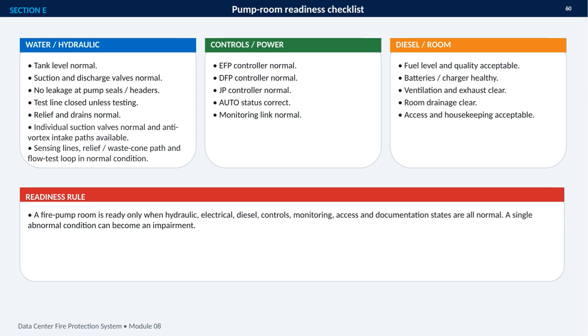Next, the electric fire pump, diesel fire pump, and jockey pump controllers should all be normal, with the correct automatic status and a healthy monitoring link. For the diesel system and room, I would check fuel quality and level, batteries and charger condition, ventilation, exhaust, drainage, access, and housekeeping. The key rule is simple. Hydraulic, electrical, diesel, controls, monitoring, access, and documentation must all be in an acceptable state. A single abnormal condition can turn an otherwise functional pump room into an impairment.